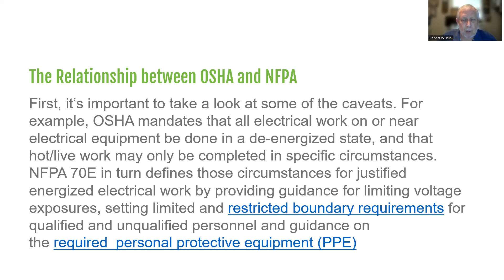First, it's important to look at some caveats. For example, OSHA mandates that all electrical work on or near electrical equipment be done in a de-energized state, and that hot live work may only be completed in specific circumstances. NFPA 70E in turn defines those circumstances for justified energized electrical work by providing guidance for limiting voltage exposures, setting limited and restricted boundary requirements for qualified and unqualified personnel, and guidance on required personal protective equipment.